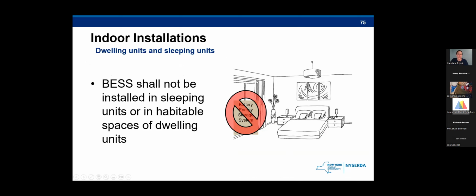So continuing on, the next two slides are two requirements that are only for indoor installations. The first one is called the dwelling units and sleeping units, and this is basically stating that energy storage cannot be installed inside a dwelling location. If an energy storage system fails, it could release some sort of toxic fume that could overcome a human pretty quickly. So we really don't recommend putting these into your bedroom or anywhere else where people may be living. They should be separated in their own area. No one's usually sleeping next to their boiler either. You don't necessarily want to sleep next to an energy storage system.